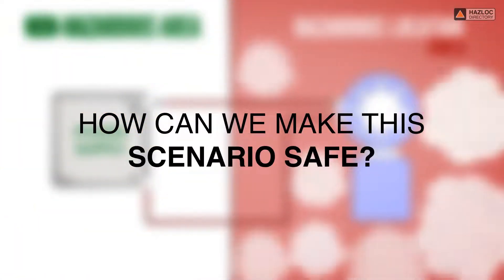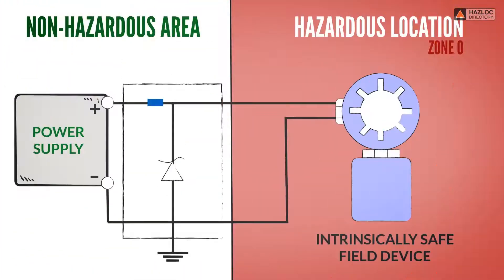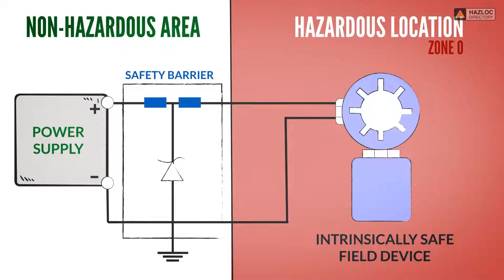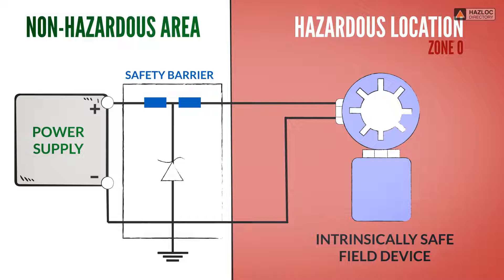How can we make this scenario safe? What's missing is an intrinsic safety barrier called simply an intrinsically safe associated apparatus or an energy limiting device. The safety barrier keeps the thermal and electrical energy below that which could create an explosion.